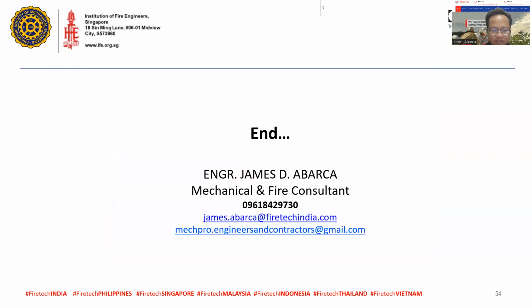Okay, so yep, I think that's all for me. That's all for my presentation. You have just learned about water mist system. That water mist system is a water-based high-pressure system. That's a good alternative for clean gas suppression, sprinkler, or conventional deluge system. And it's very, very effective and economical because you're dealing with smaller diameter of pipes, smaller pump room, smaller water tanks. Okay, and since you're using stainless steel, there's no problem in corrosion.